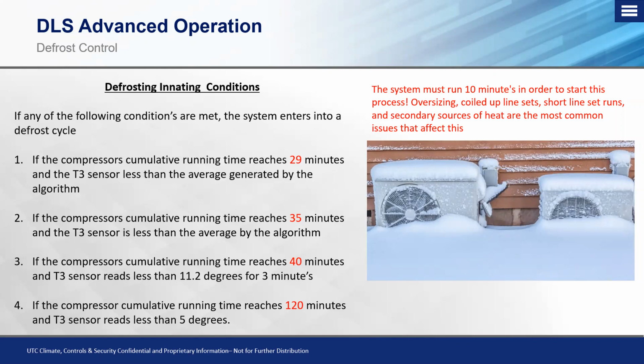The third condition is going to be if that compressor's cumulative runtime reaches 40 minutes and now the T3 sensor reads less than 11.2 degrees for 3 minutes. So we're running much longer now, and we're saying we're not going to look at that average generated by the algorithm. We're now going to look, okay, we've been running 40 minutes. I need to see if that sensor is below 11.2 degrees for a 3-minute time period. If it is, I'm going to start a defrost cycle. If it isn't, I'm not going to initiate a defrost.